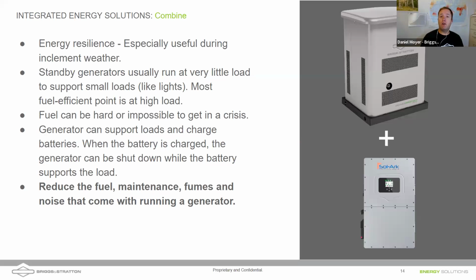If you do go into one of our generators and you look at the histogram, or the rate at which the load of the generator has been run, a lot of times, even though we put a 22K generator on your house, most of the time the generator is only running at 2,000 watts or 3,000 watts to support the base loads of the house. The reason we size them much larger is to start motor loads. Well, Daniel, I've got to comment quick on that, and I think that's great.